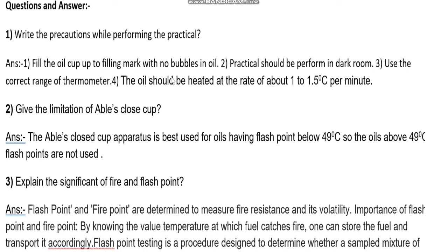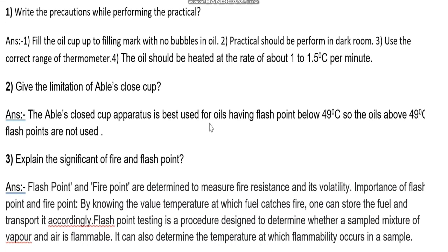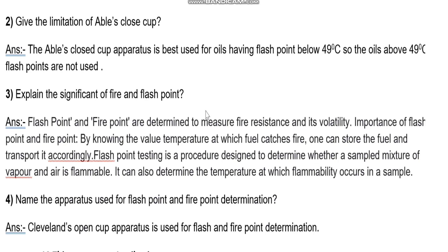Precautions: first, fill the oil cup up to the filling mark with no bubbles in the oil. Second, the practical should be performed in a dark room. Third, use the correct range of thermometer. Fourth, the oil should be heated at the rate of about 1 to 1.5°C per minute. Limitation of Abel's close cup: it is best used for oils having a flash point below 49°C; oils with flash points above 49°C are not suitable for Abel's close cup apparatus.